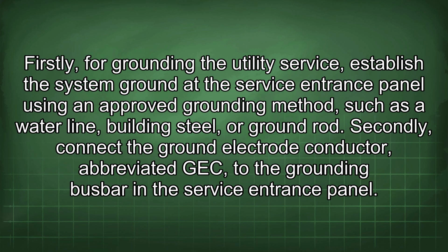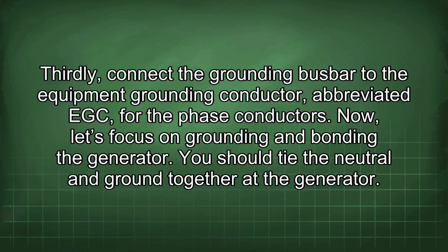Firstly, for grounding the utility service, establish the system ground at the service entrance panel using an approved grounding method, such as a water line, building steel, or ground rod. Secondly, connect the ground electrode conductor, abbreviated GEC, to the grounding busbar in the service entrance panel. Thirdly, connect the grounding busbar to the equipment grounding conductor, abbreviated EGC, for the phase conductors.